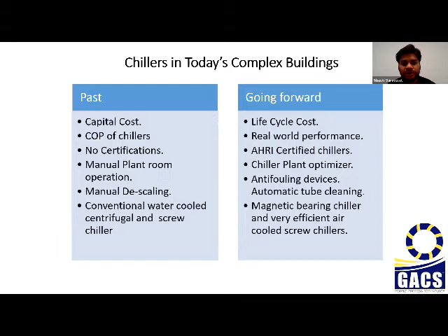Earlier there were manual plant rooms, where the manpower operated everything based on his own mindset, but nowadays a chiller plant optimizer automatically runs the complete HVAC system in a holistic manner. Earlier we did manual descaling, but now we can avoid it by putting an automatic tube cleaning system on the chiller, which further saves energy cost. Earlier we thought of conventional water cooled centrifugal and screw chillers, but with changing times there are magnetic bearing chillers which are oil free, and efficient air cooled chillers are also available in the present market.